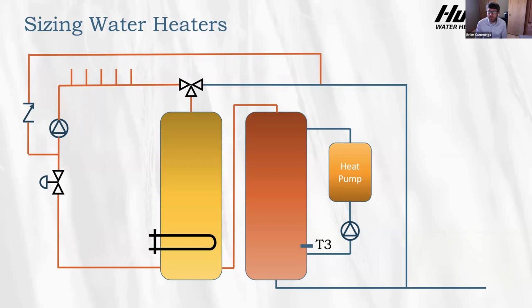that they gave a part number that was a standard off-the-shelf water heater that had 1.5-inch fittings on it. And it was non-ASME rated. So they specified, I think it was 4-inch flange fittings in all these 1,250 gallon tanks that are in the system. And then they have a water heater that's off the shelf at the very end. So you're definitely going to have a pressure drop across there. And I've seen that mistake a couple times.